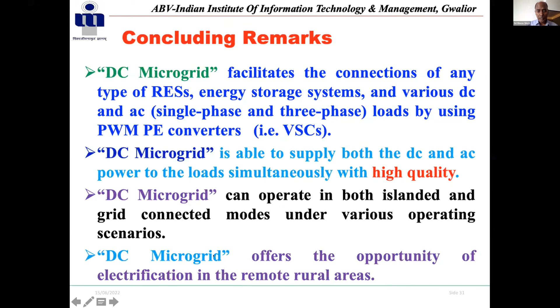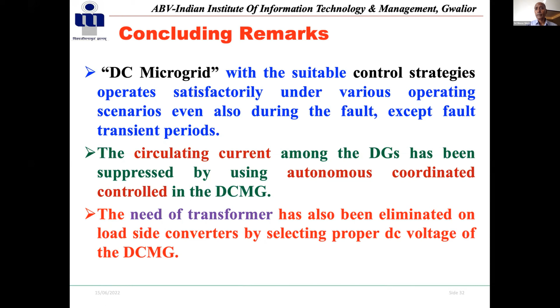The circulating current was one of the concepts where many generations are happening, so there's a possibility that circulating current will flow, which can be very effectively controlled by autonomous control. The DC microgrid should not have circulating current, because one source is generating and another is charging; it should be going to the load ends. So the need for a transformer has also been eliminated in various places. Whenever AC-DC conversion of loads and power is required, in many cases only the VSC control voltages can be used.